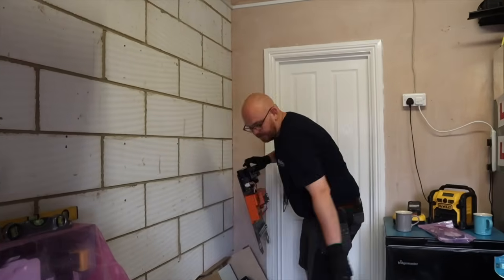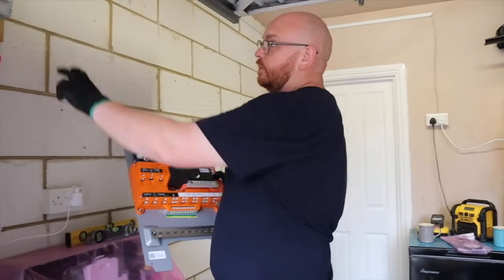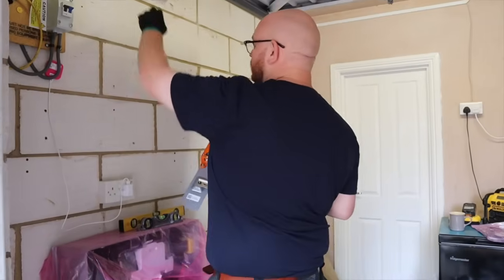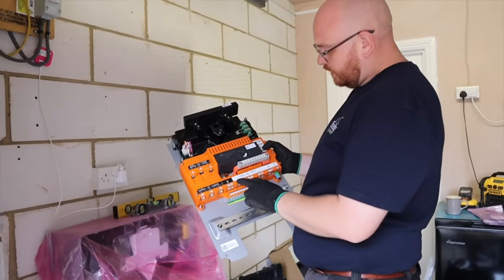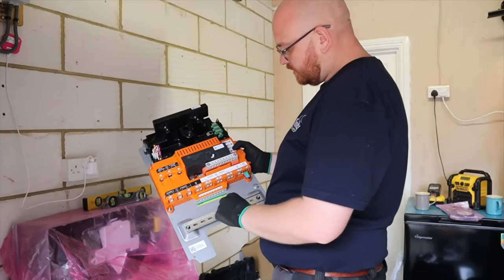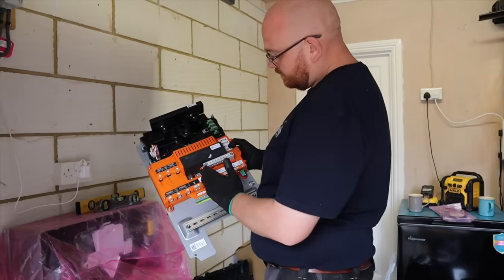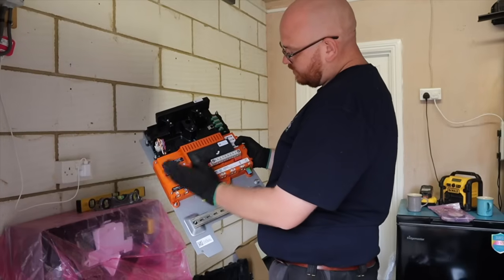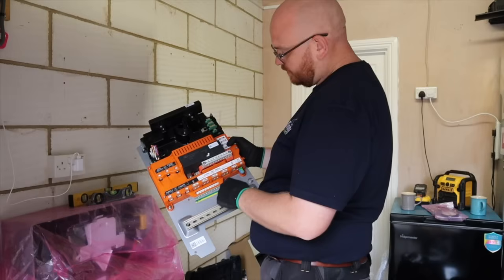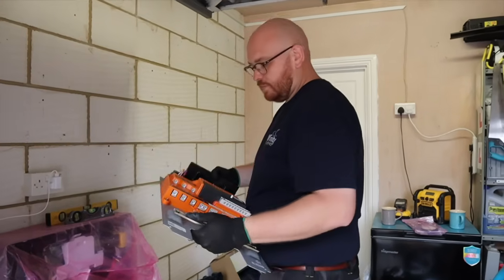With the Tesla we don't have to split off essential supplies at all. Your supply goes into here, directly from the main switch, and then comes out to your consumer unit. We can also tap off this and create our own little circuit consumer unit inside. There's a main switch going to power the Powerwall, and in the event of a power cut the grid section gets cut off so we can carry on using power from the battery. This contactor stops any flow of power going back down to the grid, keeping the house running in the event of a power cut.